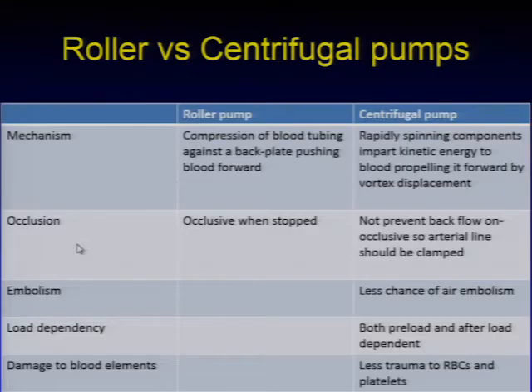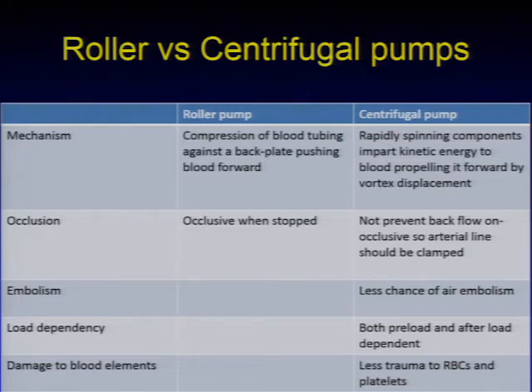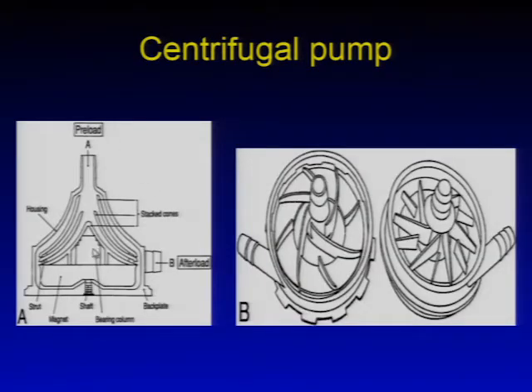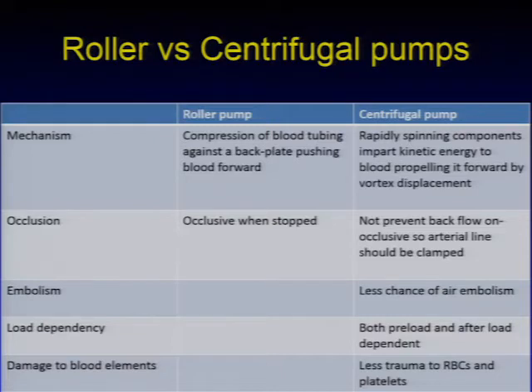The essential differences between roller pumps and centrifugal pumps: the roller pump compresses blood tubing against a back plate pushing blood forward, whereas the centrifugal pump uses rapidly spinning components like a cone or vane to impart kinetic energy to blood, propelling it forward by vortex displacement. Roller pumps are occlusive when stopped, preventing backflow automatically. Centrifugal pumps do not prevent backflow, so the arterial line must be clamped when stopped. Chances of embolism and trauma to RBCs and platelets are less with centrifugal pumps, which are both preload and afterload dependent.